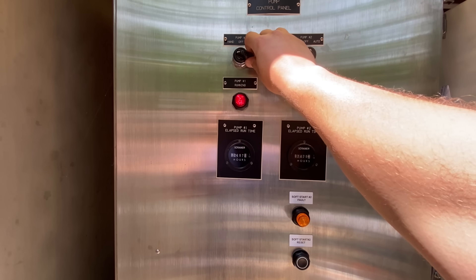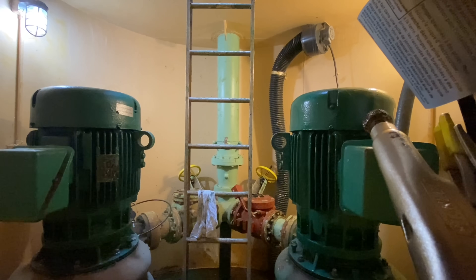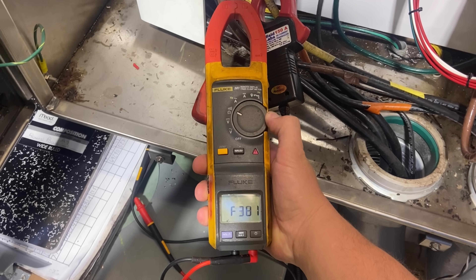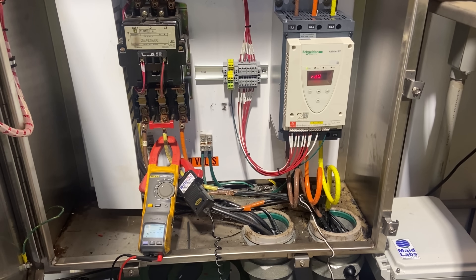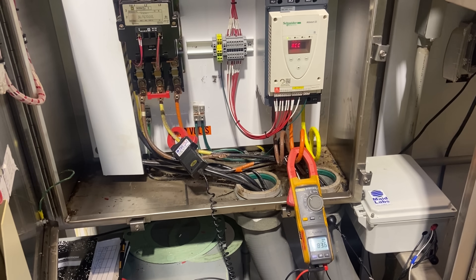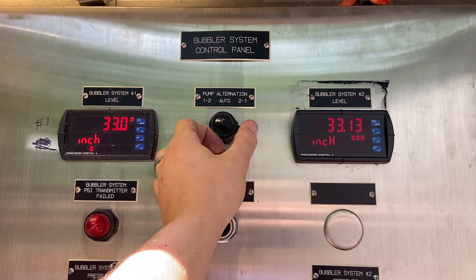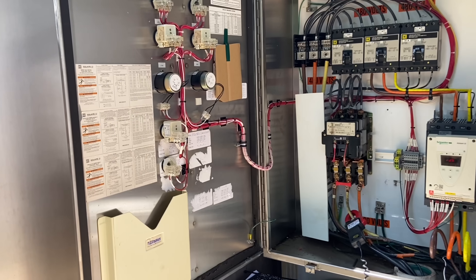Let's have a comparison between the old and the new. Now let's look at the difference in current when starting. With a regular motor starter, you can reach currents of eight times the FLA. We got 383 amp peak — I do have the meter set to peak current. And on our soft start, 83 amps. So that's a huge difference — a lot less strain on your electrical system. Everything seems to be working. Put our alternator back in auto so both pumps run like they should. Always put your pumps back in auto if you don't want the operators to be mad at you when you start spilling things everywhere.